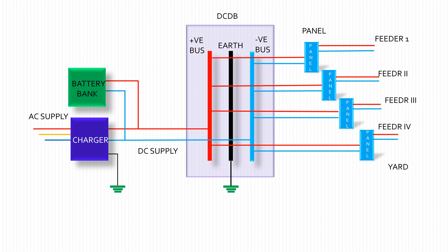But when both DC terminals become grounded, it will create a short circuit and total DC of the substation fails. In this situation, power feeding is stopped mandatorily by tripping of the circuit breaker manually. Such a case leads to very complicated situations as the fault locator does not work at all. In that case, a total shutdown of the substation is required to detect the fault, which is also a time-consuming task.